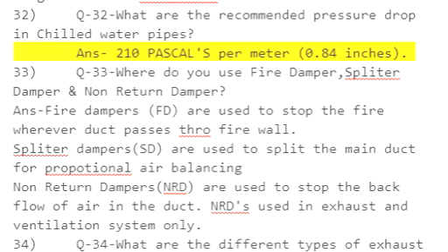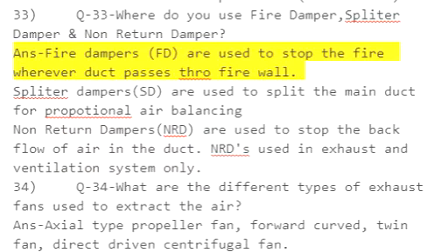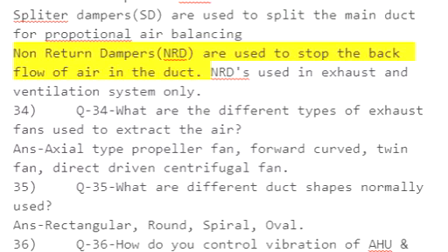Q32: What are the recommended pressure drops in chilled water pipes? Answer: 210 pascals per meter (0.84 inches). Q33: Where do you use fire damper, splitter damper, and non-return damper? Answer: Fire dampers (FD) are used to stop fire wherever duct passes through a firewall. Splitter dampers (SD) are used to split the main duct for proportional air balancing. Non-return dampers (NRD) are used to stop the back flow of air in the duct; NRDs are used in exhaust and ventilation systems only.